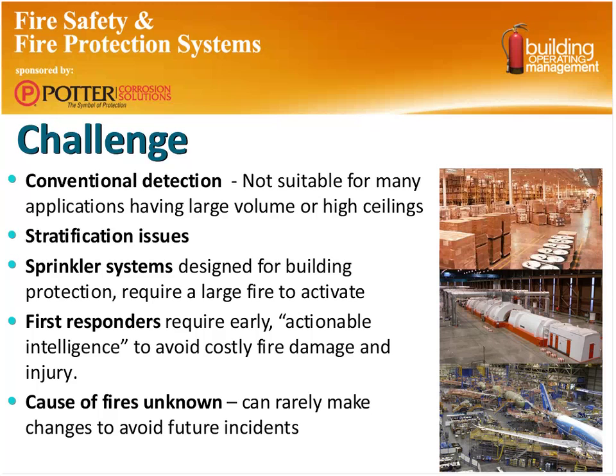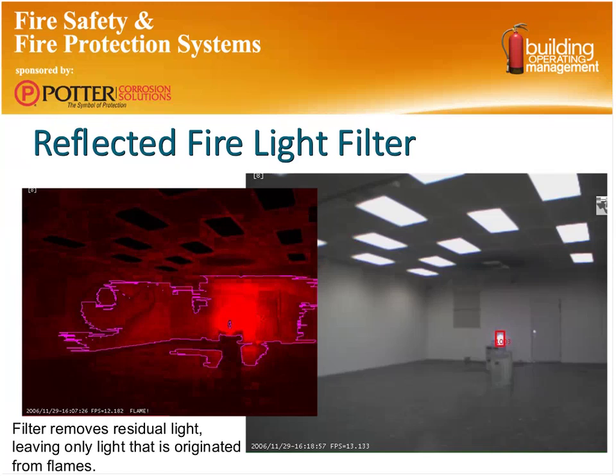Sprinkler systems, well, what are those there for? Probably mainly to protect the building, to retain the building and maintain a safe path of egress during an evacuation. We also have a couple other things that we want to try to do, and that's give more information to our first responders, the fire department, and it would in some cases be nice to know if a fire started, how did it start? Well, there are ways to do that through the intelligence of using a video camera image with some analytics built into it.